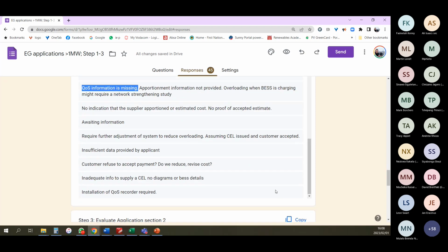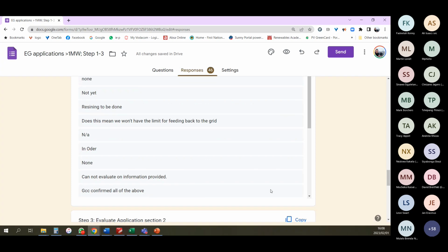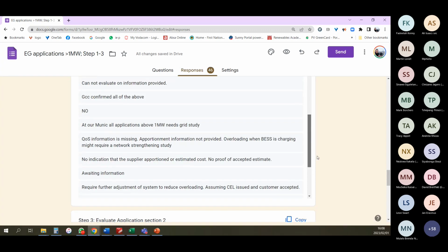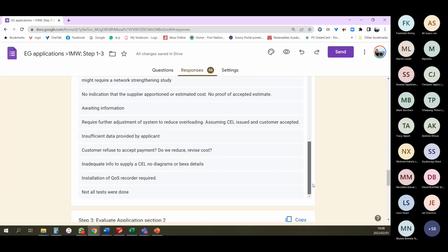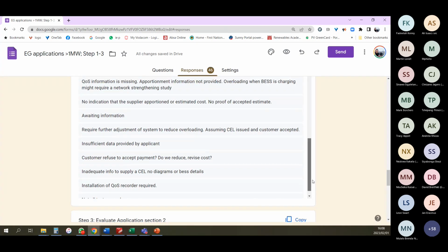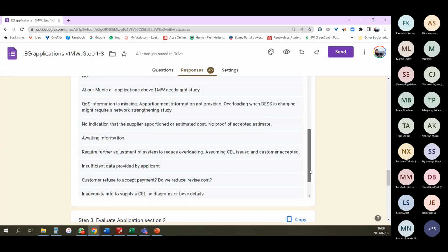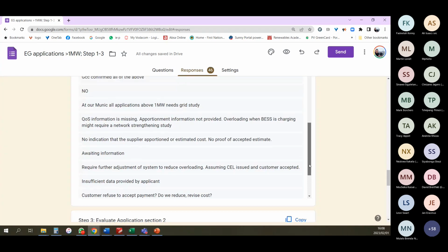Okay. Interesting that somebody speaks about the grid code compliance, because this report that I've shared is actually a grid code compliance. There's nothing about the distributor network and how that was modeled. There's nothing about the impact on the distributor network. So once again, that was meant just to add a little bit of a catch so that you think about this.